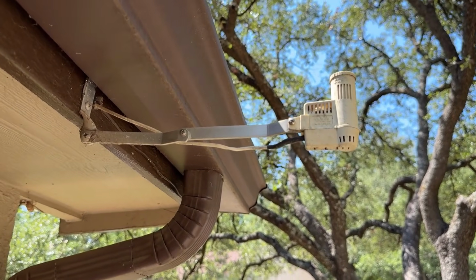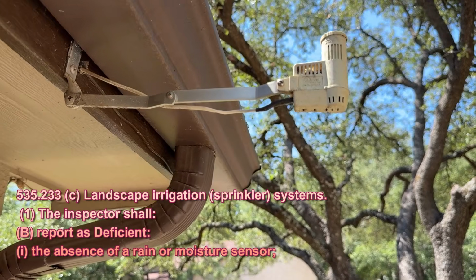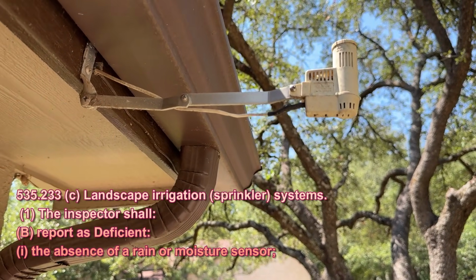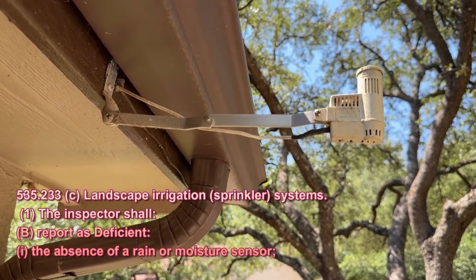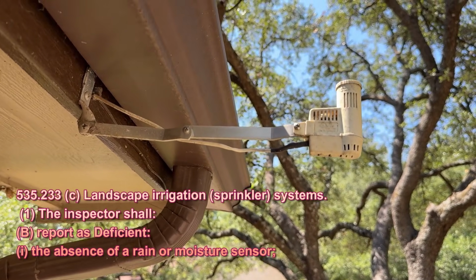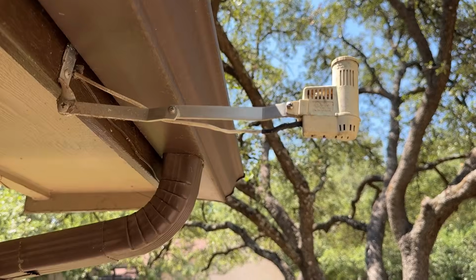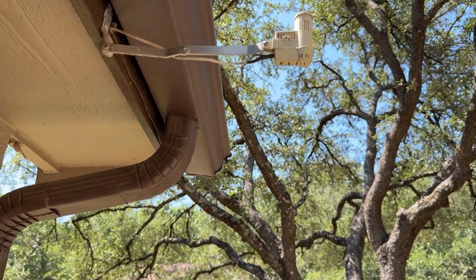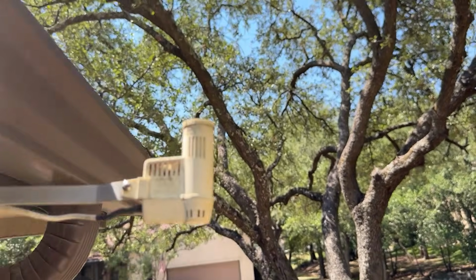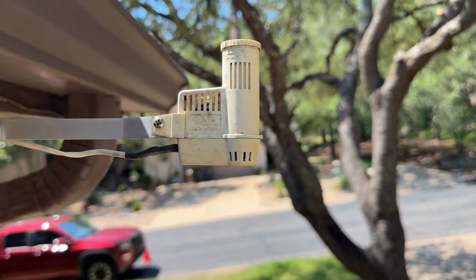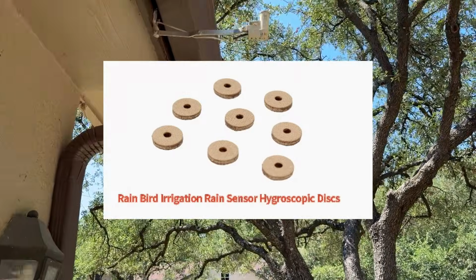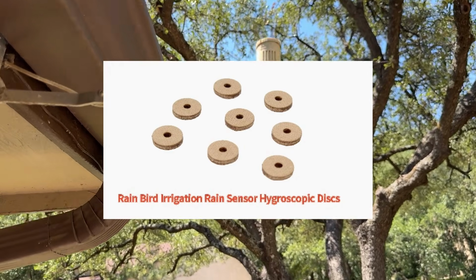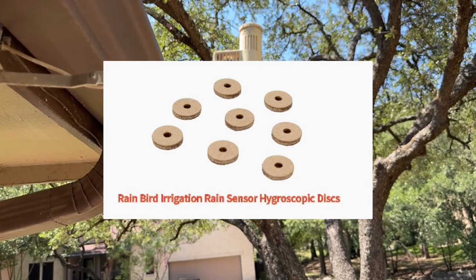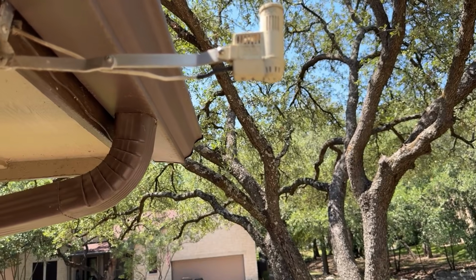This is a rain sensor device. And you can see the wire coming off there that runs back to the irrigation system control panel. If wired properly and installed properly, when it rains, water will come in to the top of this device here. Depending on the kind you have, there's a series of cardboard discs in there.